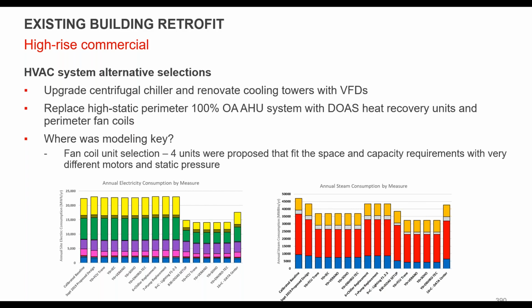They ended up keeping one steam chiller, partially because they couldn't get it out of the building because it's so huge and it was built in place. But they did upgrade both of the existing old centrifugal machines with new, variable speed units. They did a full reno on the cooling tower. So again, we modeled the cooling tower.